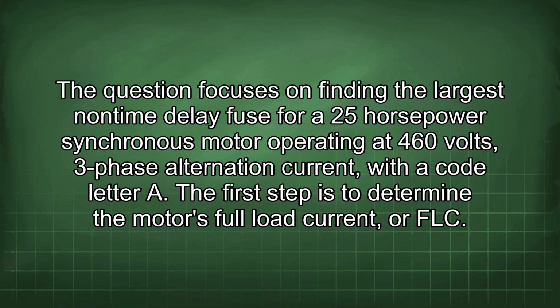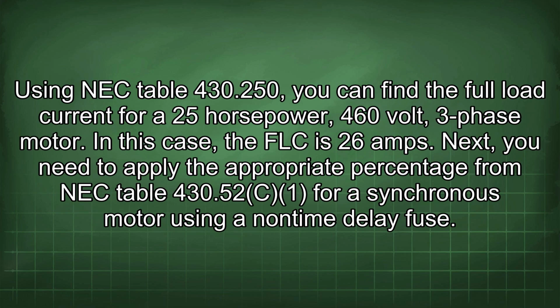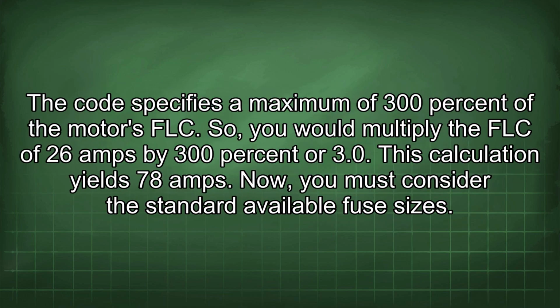The first step is to determine the motor's full load current, or FLC. Using NEC table 430.250, you can find a full load current for a 25 horsepower, 460 volt, 3-phase motor. In this case, the FLC is 26 amps. Next, you need to apply the appropriate percentage from NEC table 430.52(C)(1) for a synchronous motor using a non-time delay fuse. The code specifies a maximum of 300% of the motor's FLC. So, you would multiply the FLC of 26 amps by 300% or 3.0. This calculation yields 78 amps.